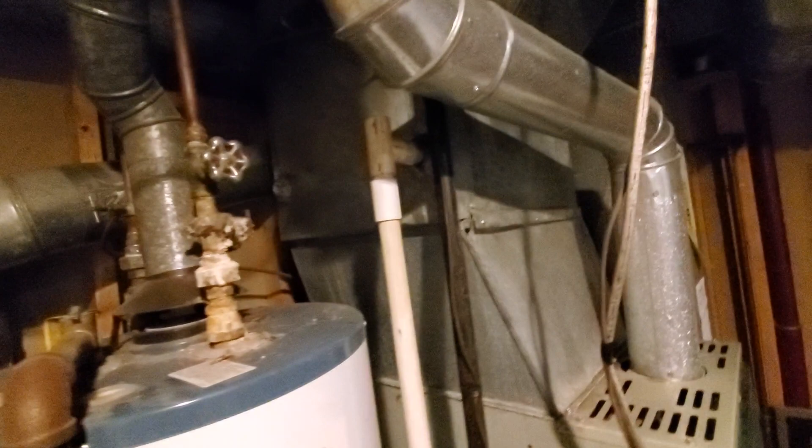We have a non-functioning humidifier on the outside. I don't see a humidistat. You see the line set, and the liquid line is a quarter inch, so it's got to be a two ton or a two and a half outside.